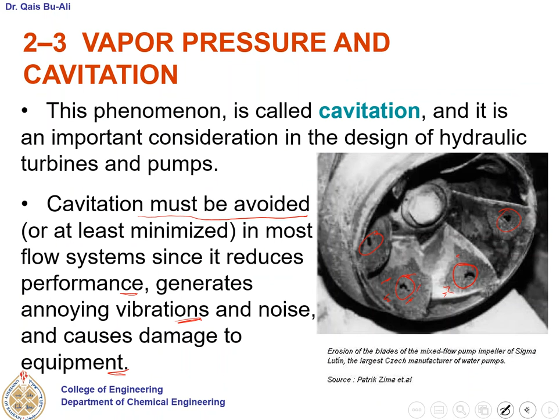So in a water distribution system, the temperature of water is observed to be as high as 30 degrees centigrade. Determine the minimum pressure allowed in the system to avoid cavitation. So I gave you this table here. As you can see, I'm talking about 30 degrees centigrade. So how much do I have to keep my pressure so that I don't have vaporization?